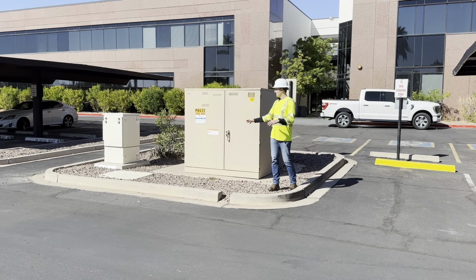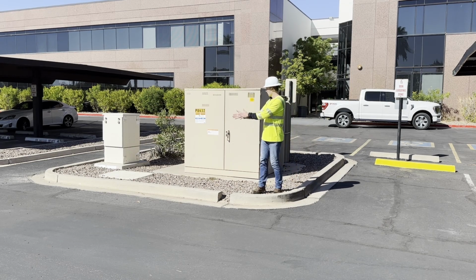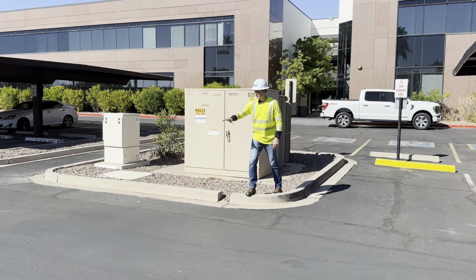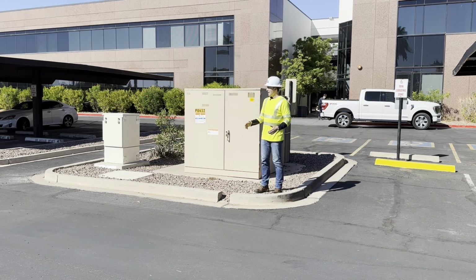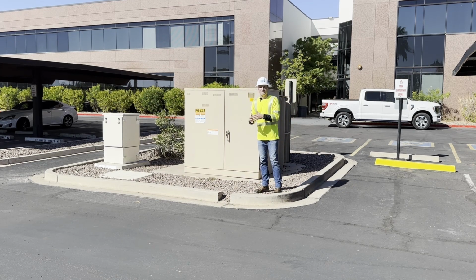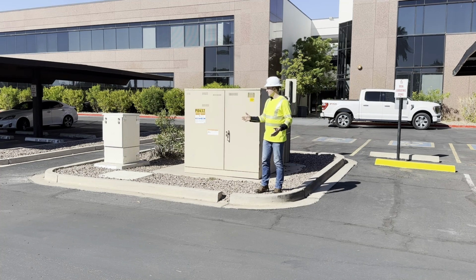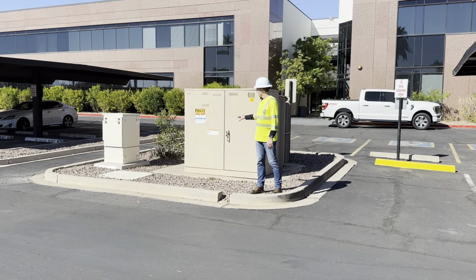As you can see here, there's this curb cut, roughly 3 feet in front of this transformer, but the utility is actually able to give them a little bit of grace here and use this as part of the clearance, because if a car is parked here, it can leave within a certain period of time. So they don't always need to have this 100% of the time clear.